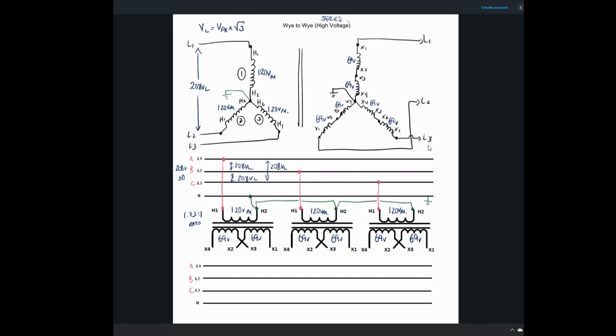So our neutral here, let me move that neutral over here because I usually have it coming out over here. So that's our neutral, right? And that is bonded to ground. Then the voltage between any line and neutral is now going to be the sum of 69 and 69. So this voltage is going to be really strange. It's going to be 138 volts on the phase from any line to neutral.